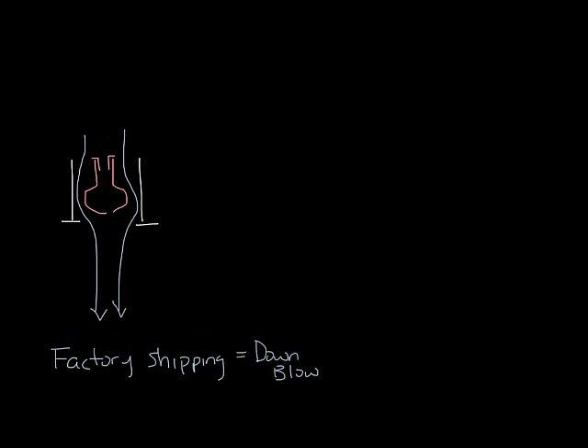In my case we weren't on a perimeter so we're looking at a cooling application and it was pointed probably in the factory default straight down at me. So what you really want is for the air to be directed across the ceiling so it can roll the room and mix into the space without dumping on people. So how would you do that with the ML?